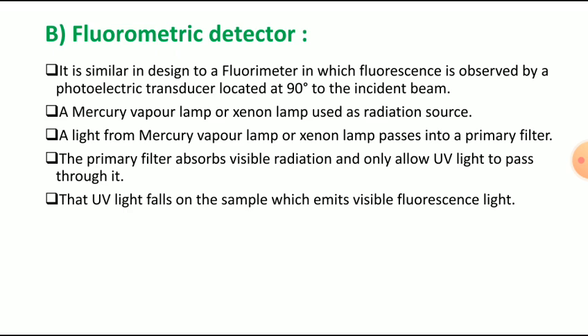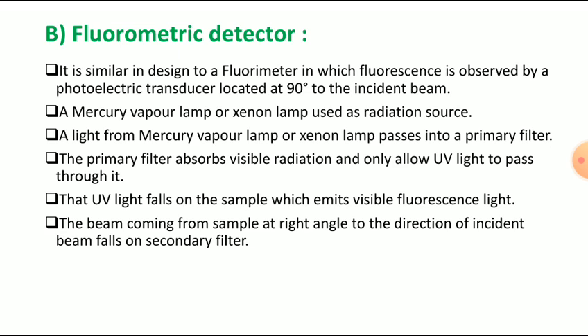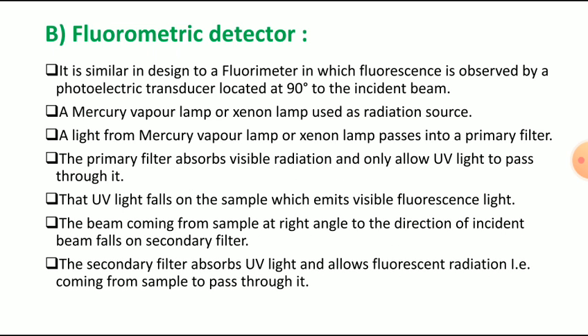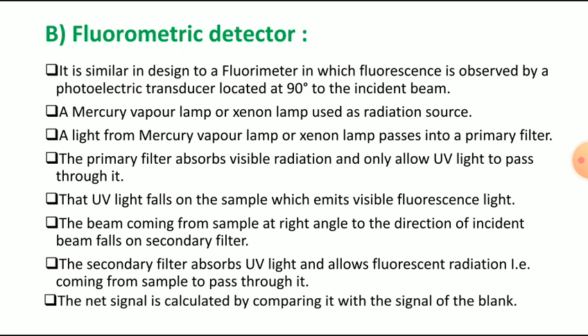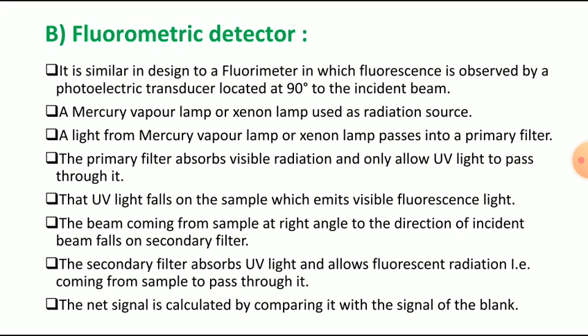The UV light then falls on the sample. The sample absorbs that UV light and emits visible fluorescence. That fluorescence light coming from the sample at a right angle to the direction of the incident beam passes through a secondary filter. The secondary filter absorbs the UV light and allows only the fluorescent radiation coming from the sample to pass through it. The net signal is then calculated by comparing it with the blank reading.